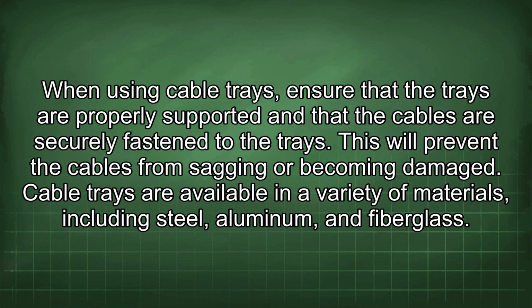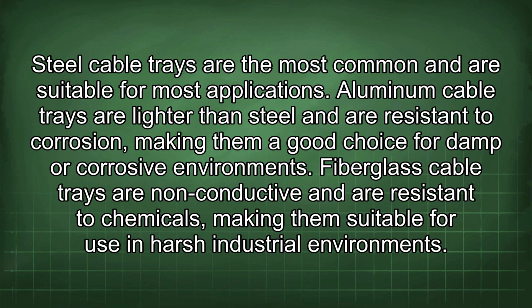When using cable trays, ensure that the trays are properly supported and that the cables are securely fastened to the trays. This will prevent the cables from sagging or becoming damaged. Cable trays are available in a variety of materials, including steel, aluminum, and fiberglass. Steel cable trays are the most common and are suitable for most applications. Aluminum cable trays are lighter than steel and are resistant to corrosion, making them a good choice for damp or corrosive environments. Fiberglass cable trays are non-conductive and are resistant to chemicals, making them suitable for use in harsh industrial environments.